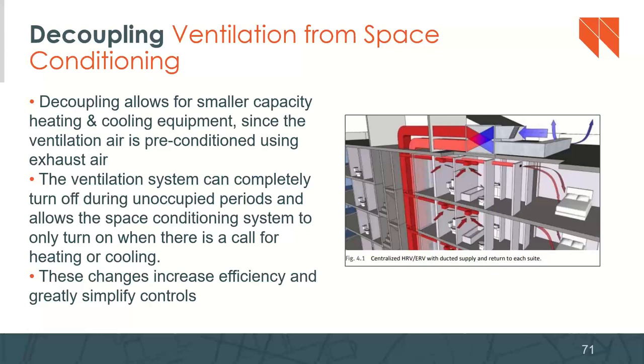So when your ventilation system is not tied to your air handler for the heating and cooling, you wouldn't have to run that air handler to distribute the air. So these changes increase efficiency and greatly simplify the controls when you decouple the ventilation system from the heating and cooling system.